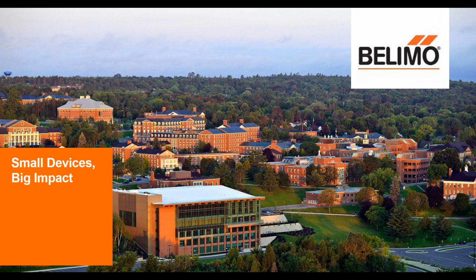The end result? Savings from optimizing chiller performance in the building using the Belimo energy valve is estimated to be over $1,200 per year with a payback period of approximately 4 years. Installation of the energy valve was completed in less than a day, resulting in minimal manpower costs. Users have improved transparency and control of the heat exchange process with the energy valve's built-in power control and delta T manager. Since its installation, the energy valve has performed flawlessly with no setbacks or breakdowns. At Belimo, we continue to ensure our small devices make a big impact in buildings.